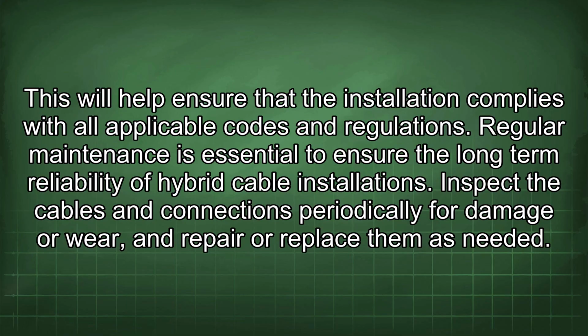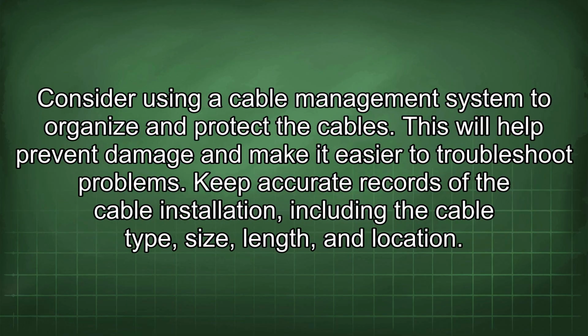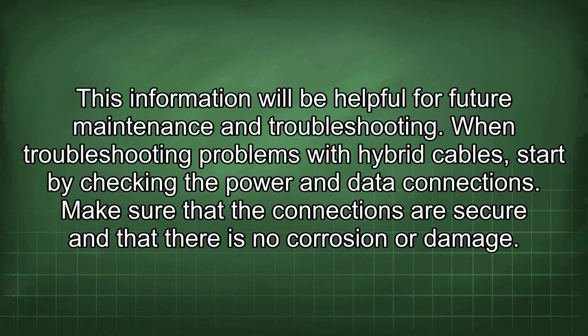Regular maintenance is essential to ensure the long-term reliability of hybrid cable installations. Inspect the cables and connections periodically for damage or wear, and repair or replace them as needed. Consider using a cable management system to organize and protect the cables. This will help prevent damage and make it easier to troubleshoot problems. Keep accurate records of the cable installation, including the cable type, size, length, and location. This information will be helpful for future maintenance and troubleshooting.